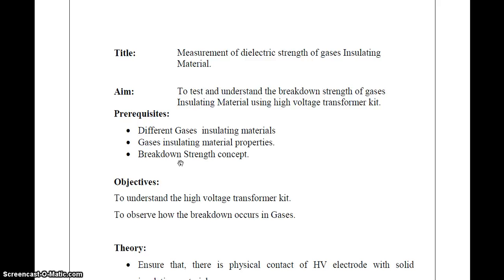Ionization of air in the air gap decreases the spark over voltage, and therefore ultraviolet ionizing radiation should be avoided for correct measurement. After testing, the spheres should be properly cleaned to maintain a polished surface. No conductor or body having a conducting surface shall be near the sparking point of the high voltage sphere than the distance given by IS. The time interval between consecutive flashovers should be large enough to avoid appreciable heating of the sphere.